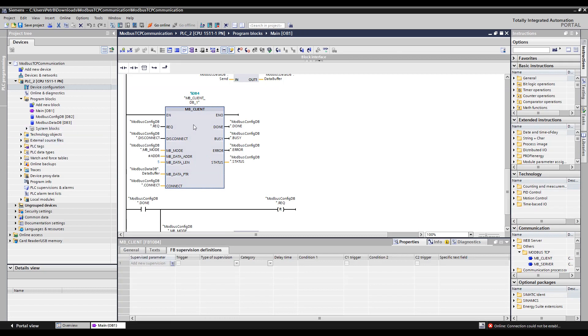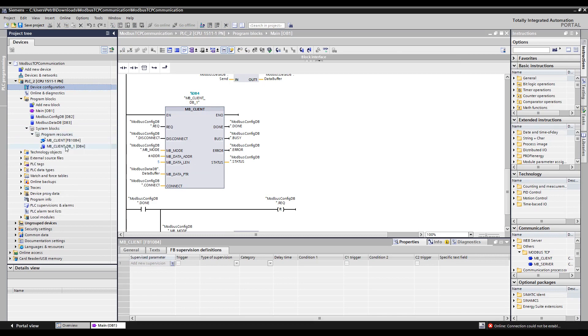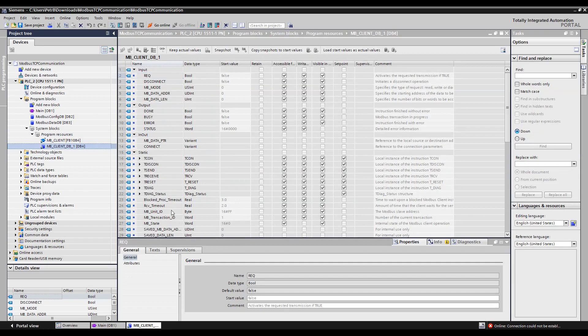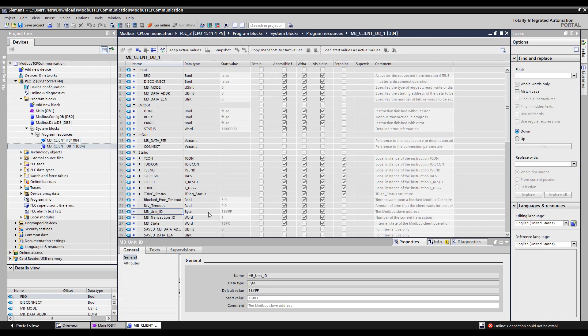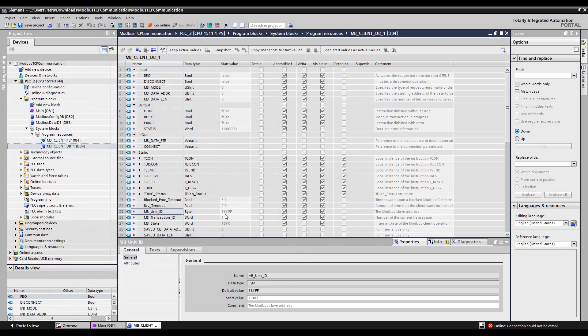When you create the MB_Client in System Blocks it automatically creates a function block DB — here it's DB4. Open that DB and set the MB_Unit_ID, which is the unit ID of the other device. In the Modbus Slave software you can see it's set to 255 (0xFF). This number depends on your device — check your datasheet; sometimes it's 1, sometimes it's 255.